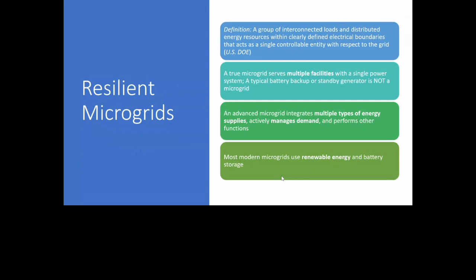None of this is done by human hands going out there and pressing buttons or disconnecting things or putting different wires in. The microgrid controller can sense when the SDG&E grid is unstable and goes down, and there's a latency effect of about 5 to 10 seconds where it then turns off of the SDG&E grid and fully powers up off of the batteries and solar.